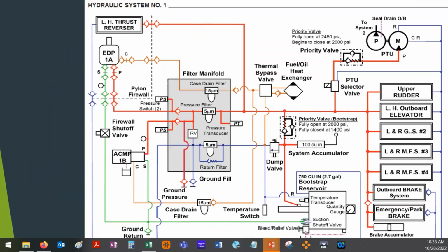On both those pumps, you can see there's an orange line coming out of them. That's the case drain. 1A pump goes to a case drain filter before going to the heat exchanger and then back into the return side of the system. Same thing with the 1B pump, case drain filter, heat exchanger, back to the return side. And then on the return side, everything in blue, when it comes back through the blue manifold here.